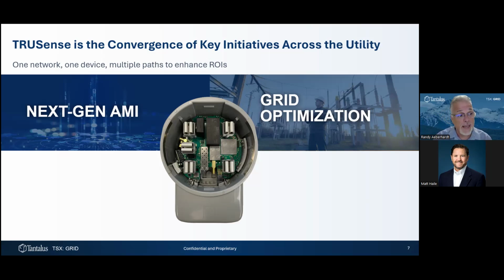So again, this is the basis for measuring. The idea is that you're measuring at the interconnection point between your distribution grid and the premise you're supplying energy to, so you see exactly what's happening with the DERs behind this device—how they're affecting power quality, and what kind of energy they're pushing back or consuming.